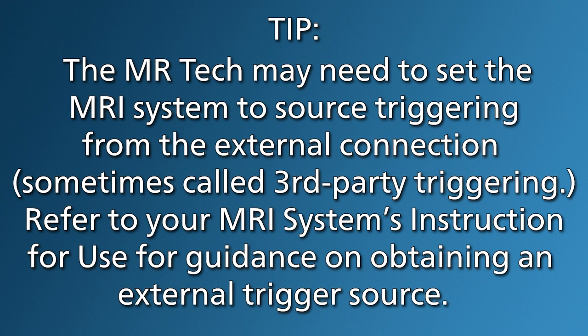The MR Tech may need to set the MRI system to source triggering from the external connection, sometimes called third-party triggering. Refer to your MRI system's instruction for use for guidance on obtaining an external trigger source.